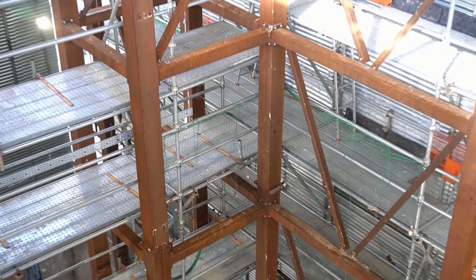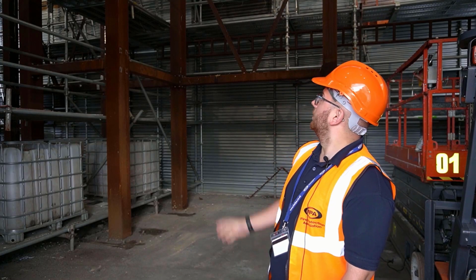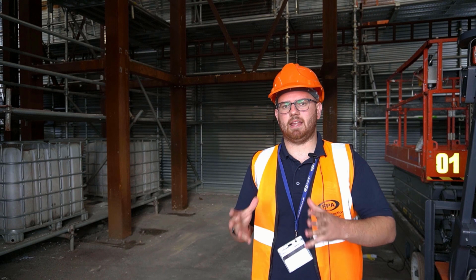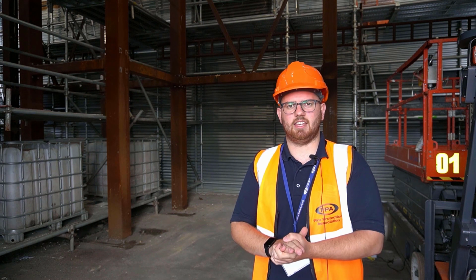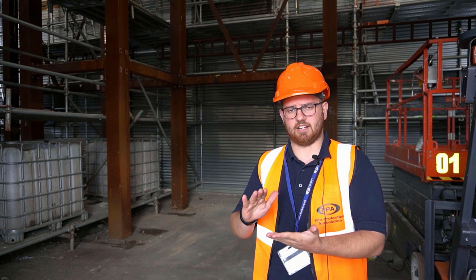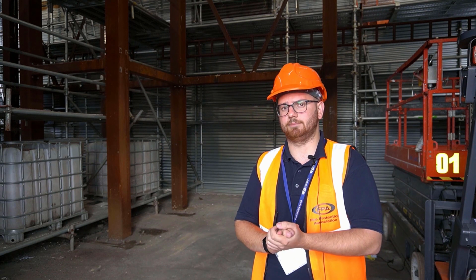So this is what you'll get when you arrive at the FPA as a prospective client for a BS8414 test. So essentially you have a big steel frame, which is essentially the blank canvas that every single 8414 test starts with. Onto that, the first thing that gets added is the METSEC frame that we spoke about in the other rigs, and then you will attach a sheathing board onto that, and then any bracketry, and then finally the insulation and the facade onto that.